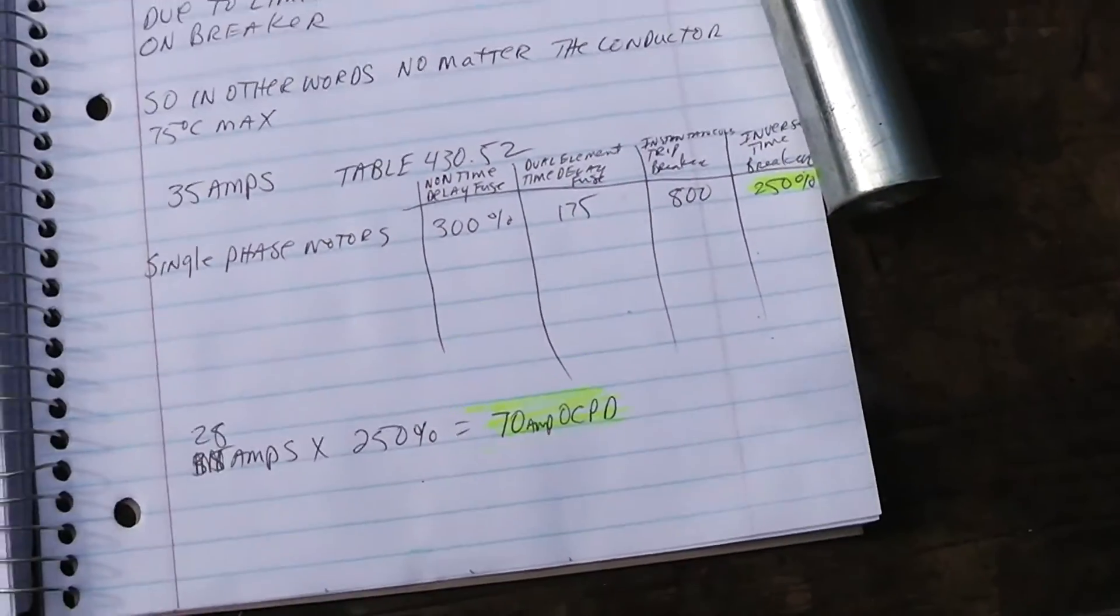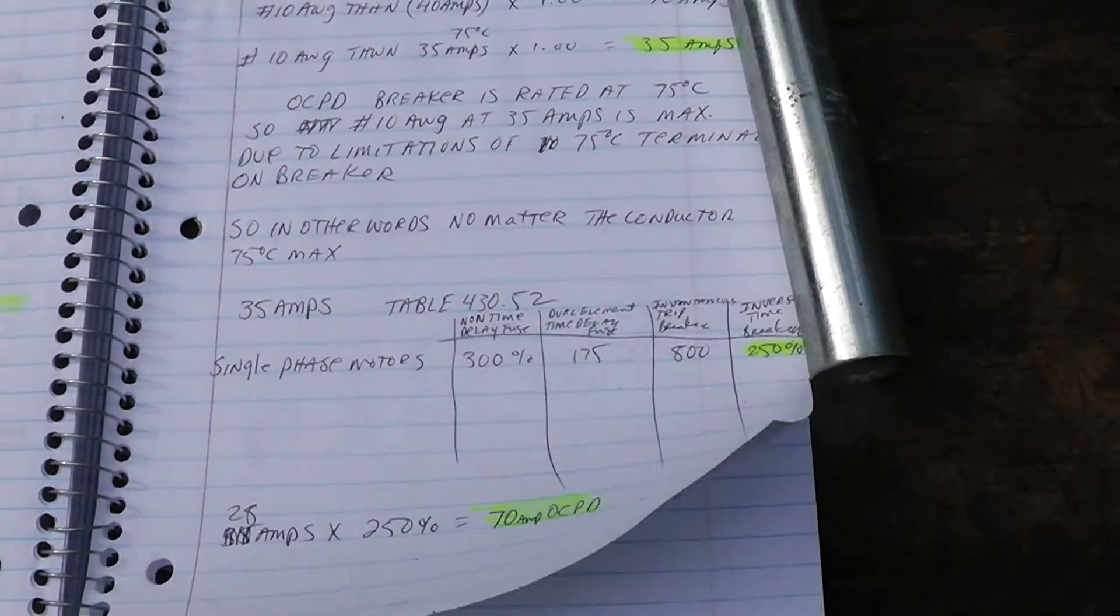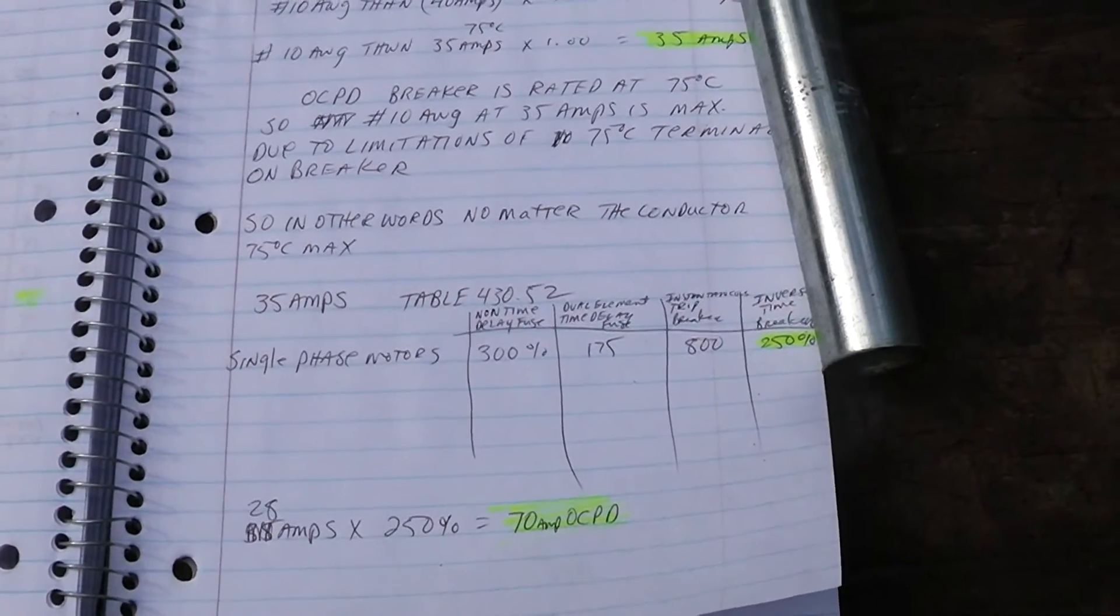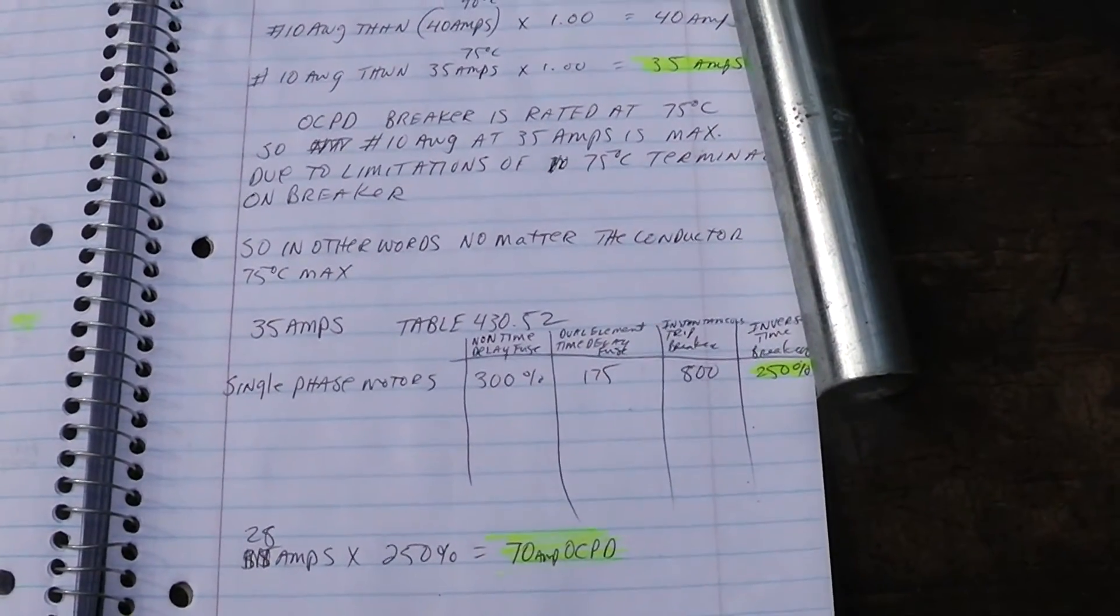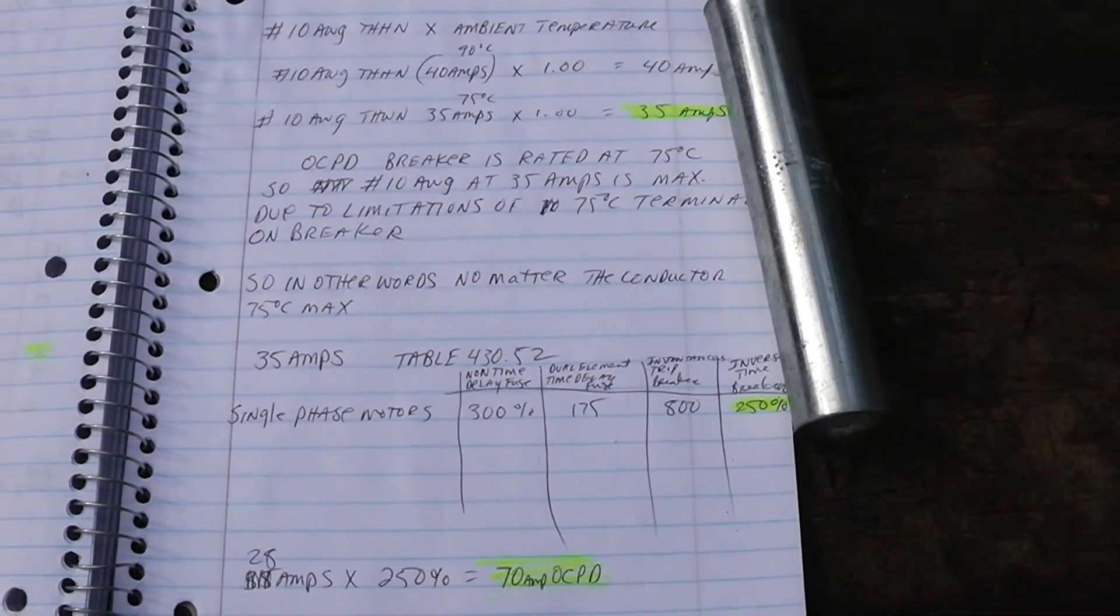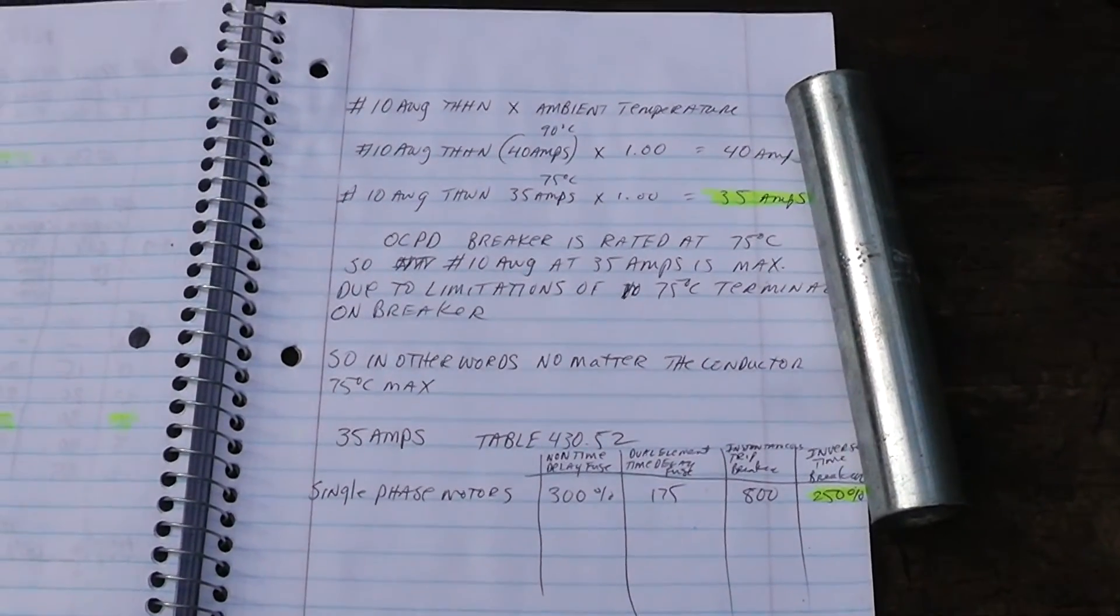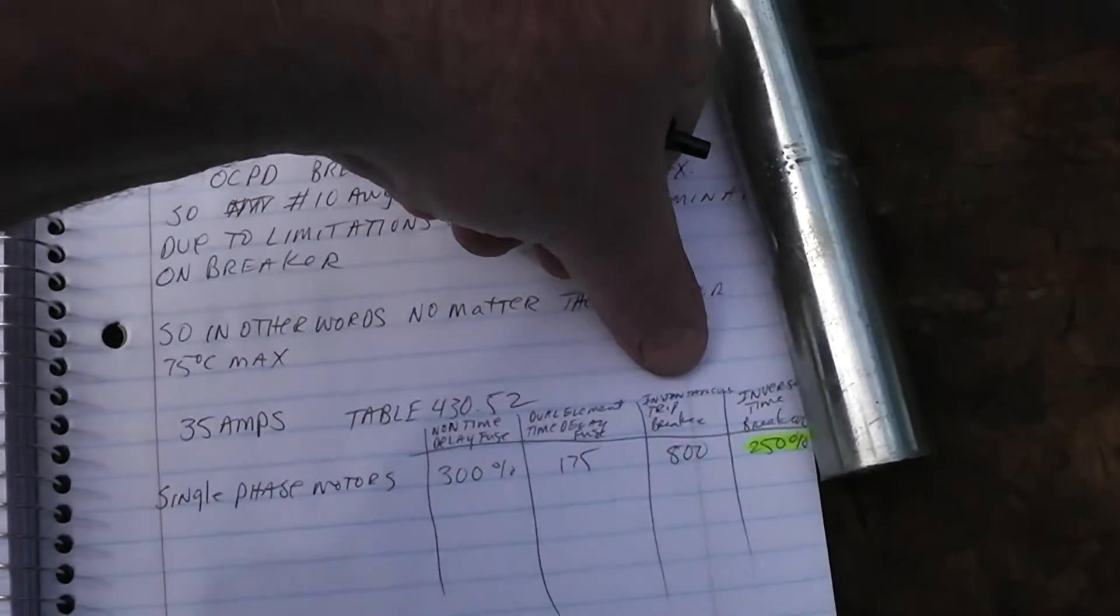I know a lot of people get a 5 horsepower compressor, they read the nameplate that says 28 amps, and they put a 30 amp breaker on it. It will work, but if you're going to have it inspected or if you want it to have a long service life, then you need to put that 70 amp breaker on there or use one of these fuses.